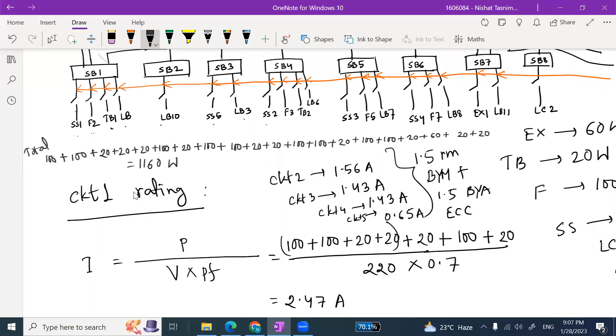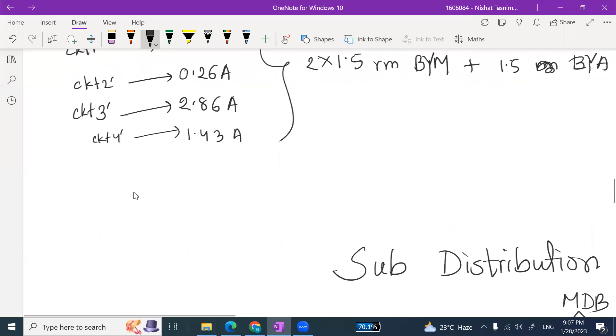Total load. So our calculated total load is 1160 watts. So 1160 into 0.7. Now total P socket load. How many P sockets were in the connection diagram? 2 P sockets, right? And we have assumed that the P socket load is 3000 watt. And we have also assumed the load factor is 0.2.